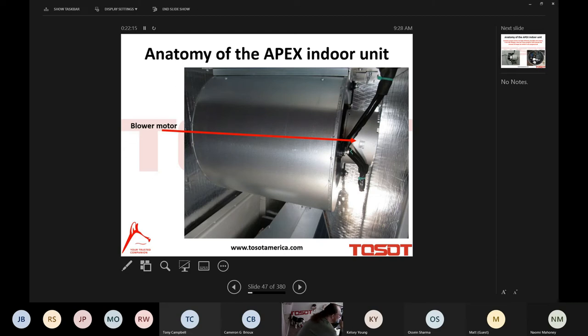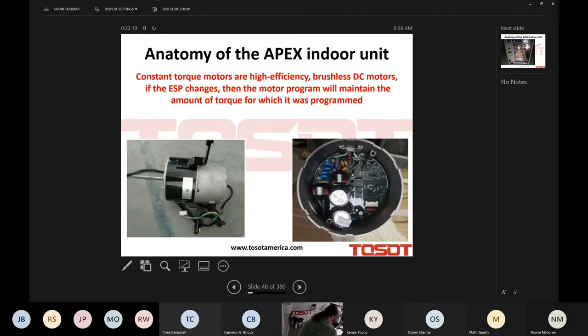The blower fan motor of the Apex indoor unit, guys, is a constant torque motor. Constant torque motors are high efficiency. They're brushless DC motors. If the ESP, the external static pressure, changes, a dirty filter, something more dramatic like a duct collapsing, that's very dramatic, then the motor program will try to maintain the amount of torque for which it was programmed. Very, very unique in that way.